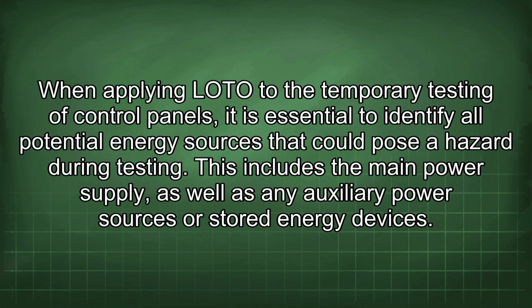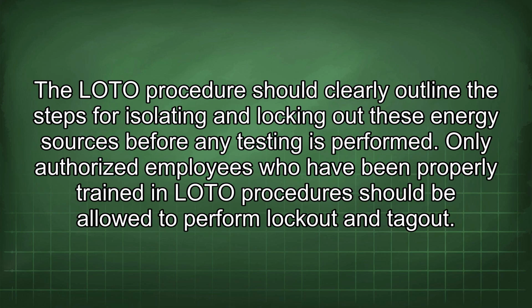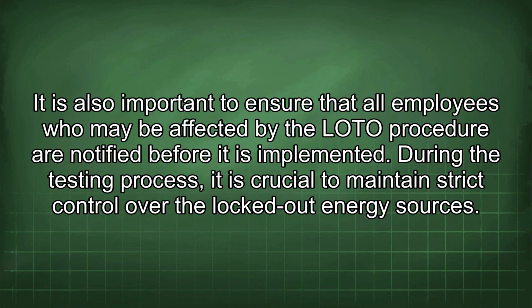When applying LOTO to the temporary testing of control panels, it is essential to identify all potential energy sources that could pose a hazard during testing. This includes the main power supply, as well as any auxiliary power sources or stored energy devices. The LOTO procedure should clearly outline the steps for isolating and locking out these energy sources before any testing is performed. Only authorized employees who have been properly trained in LOTO procedures should be allowed to perform lockout and tagout. It is also important to ensure that all employees who may be affected by the LOTO procedure are notified before it is implemented. During the testing process, it is crucial to maintain strict control over the locked out energy sources.